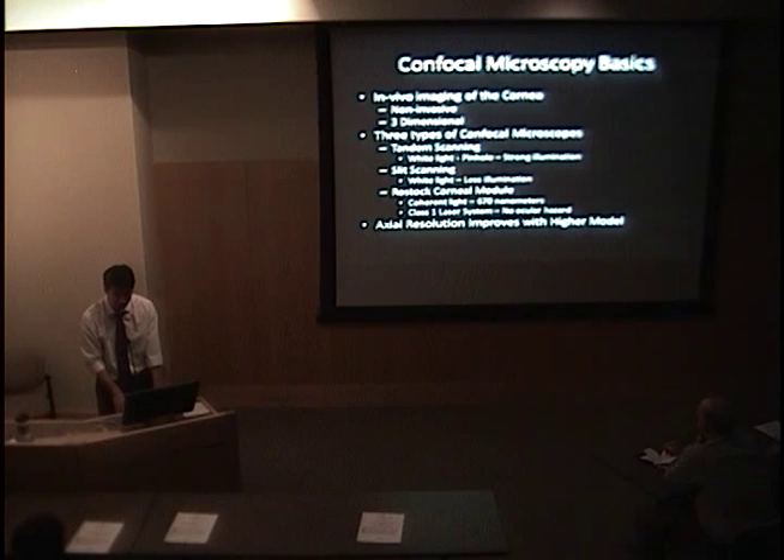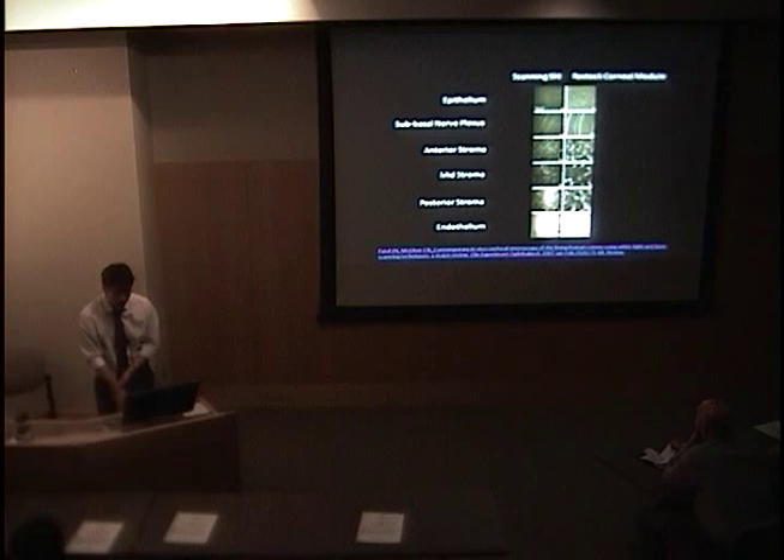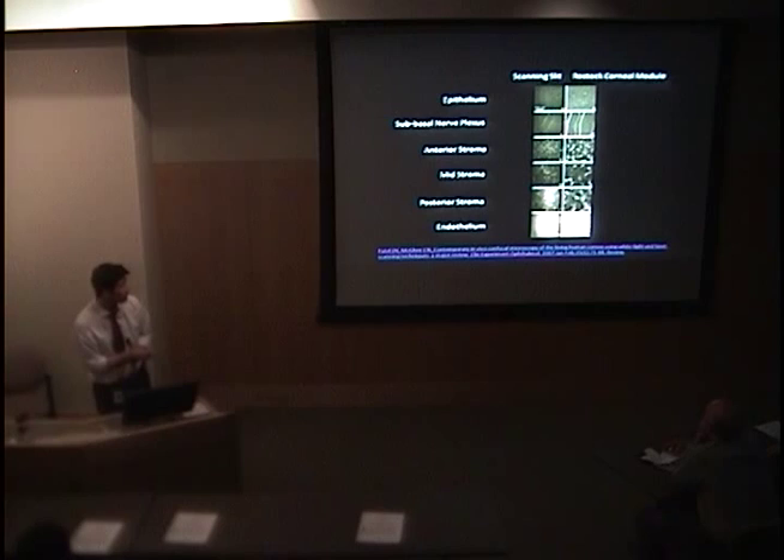The axial resolution — not the left-right resolution but the Z-direction resolution — improves as the light becomes better. The Rostock cornea module HRT3 has a 300 by 300 micron area resolution, and the axial resolution is 4 microns, which is much better than the other two. Looking at the pictures, the NIDEK is on the left and the Rostock cornea module on the right. You can see every layer of the cornea is much cleaner — starting from the epithelium, the nerves, the stroma, and then the endothelium.